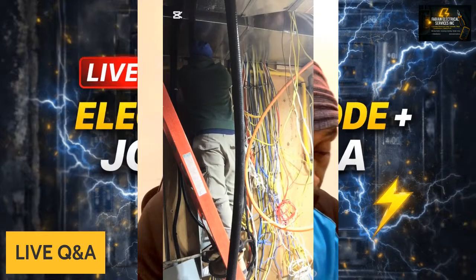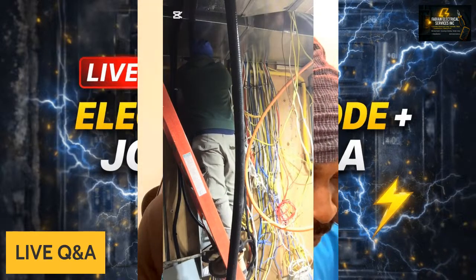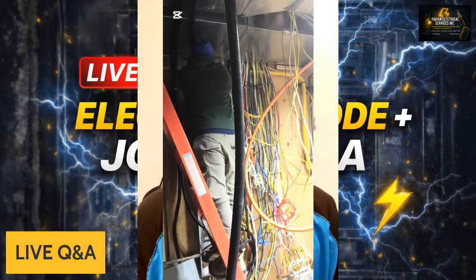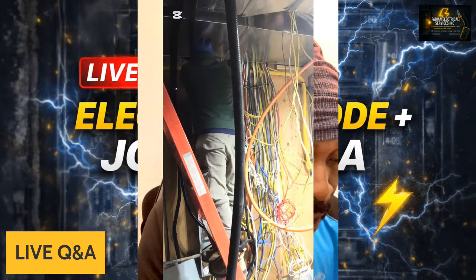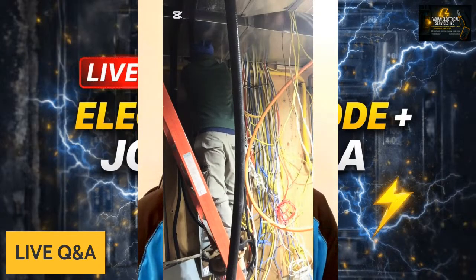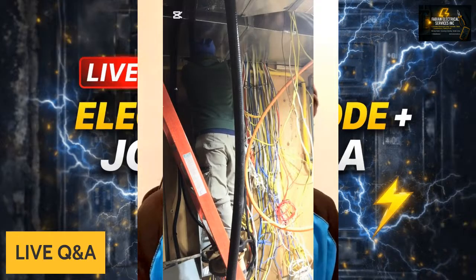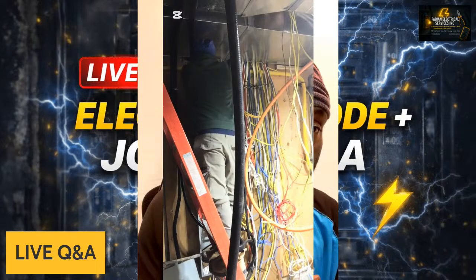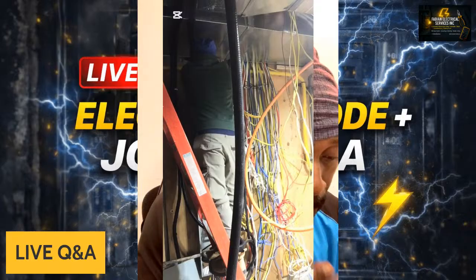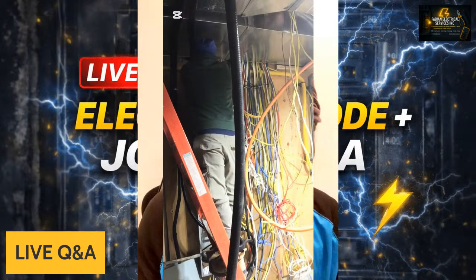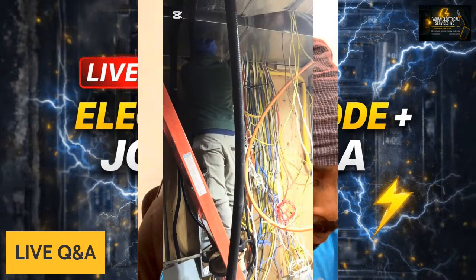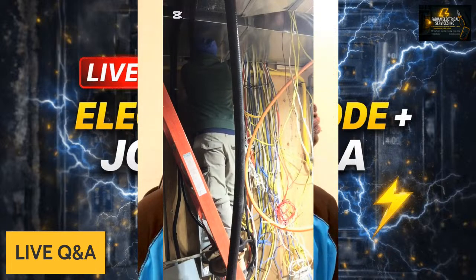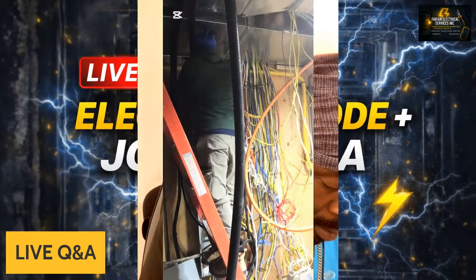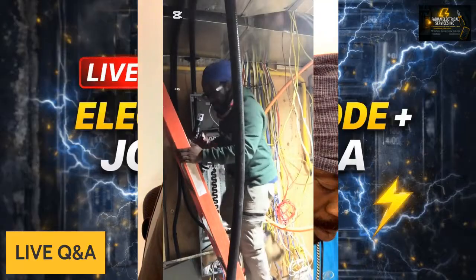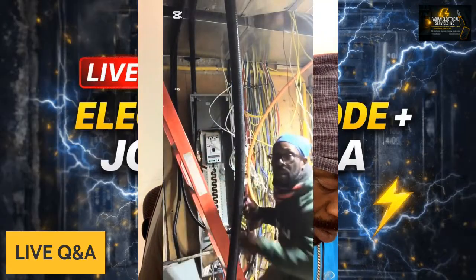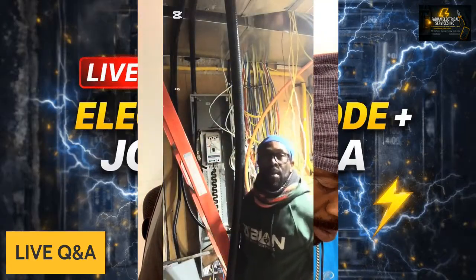So hello, welcome back to the channel. And in today's video, the main service panel is being installed as required by the code. So again, also using 250 kcmil wire twice, parallel feeds, in order to power up this service. Very important to make sure that you select the proper cable. You also have the proper panel with the proper labeling on the panel door.